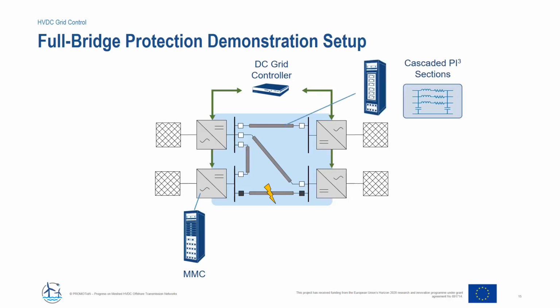The HVDC cables are represented using cascaded pi sections, also designed for wider frequency range, and this allows us to get a similar behavior within the small scale as within a full scale system, just using pi sections and not, for example, a universal line model. This we can for sure not use in our laboratory.